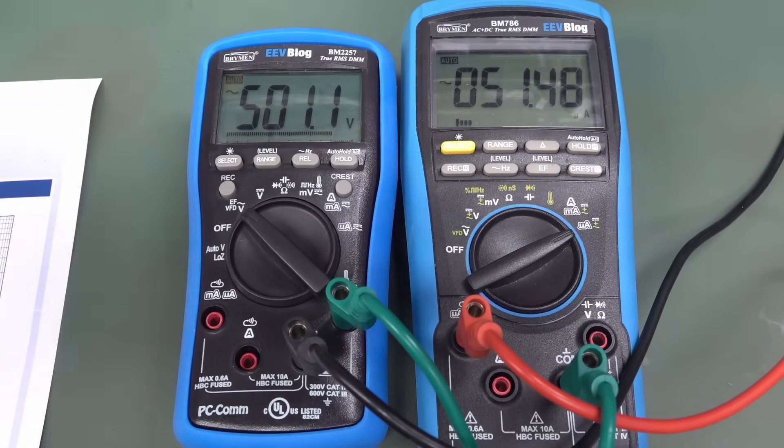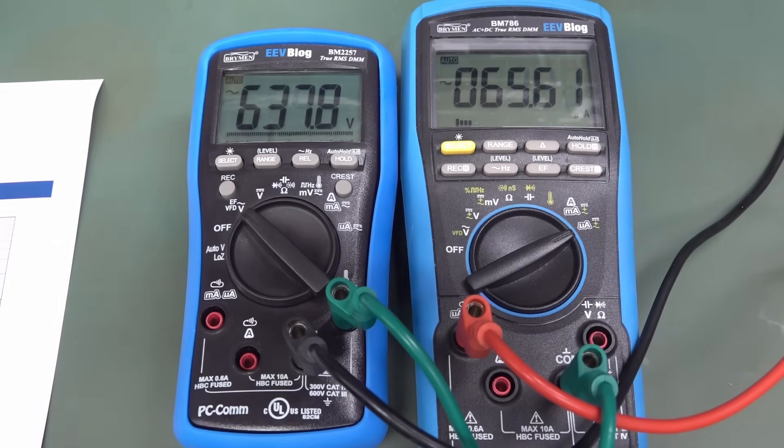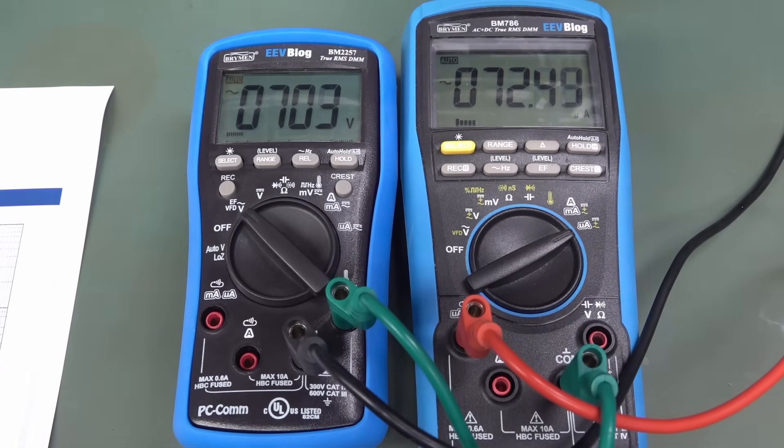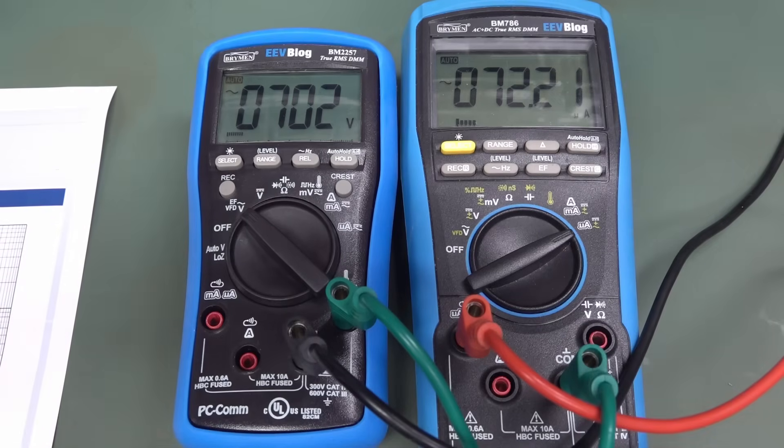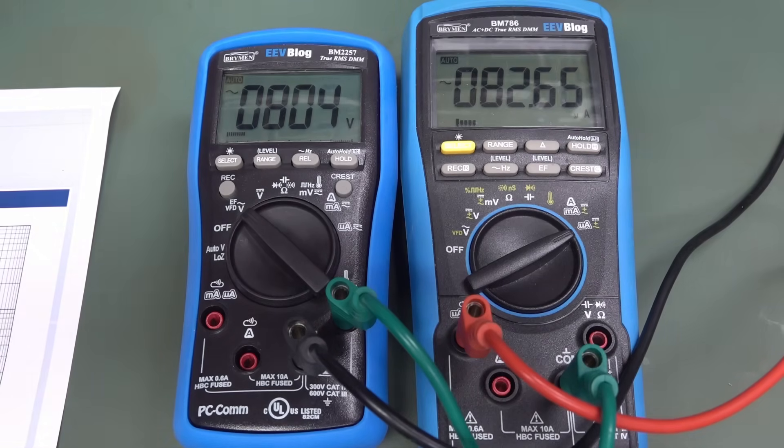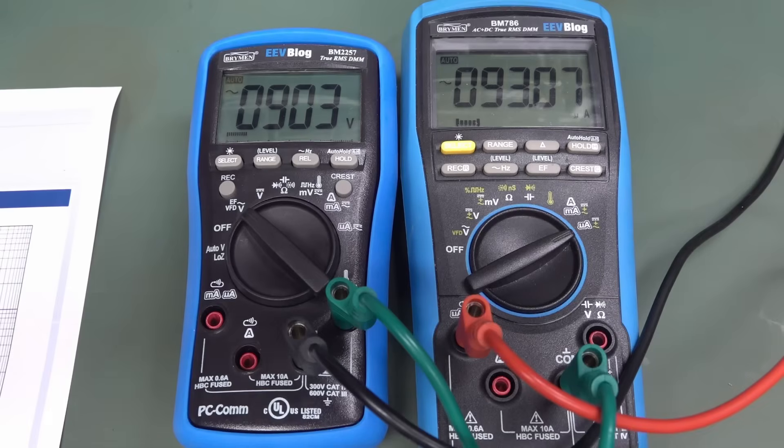500 volts. It takes time to settle down here when I switch it. It's just the nature of the response loop of the standard. 600 volts. Still pretty 10 megohms-ish, isn't it? 700 volts. Well, there you go. 72 microamps. 800 volts. So 82.6 microamps. Interesting. 900 volts. So yeah. Now the leakage looks like it starts coming into play. But really, that's nothing to quibble about.